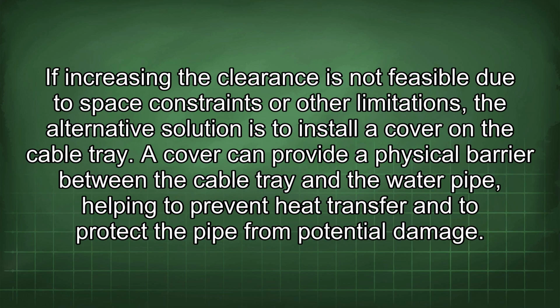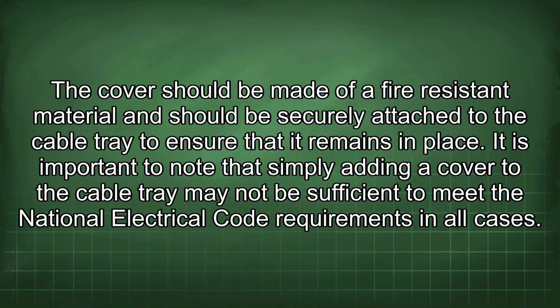If increasing the clearance is not feasible due to space constraints or other limitations, the alternative solution is to install a cover on the cable tray. A cover can provide a physical barrier between the cable tray and the water pipe, helping to prevent heat transfer and to protect the pipe from potential damage. The cover should be made of a fire-resistant material and should be securely attached to the cable tray to ensure that it remains in place.